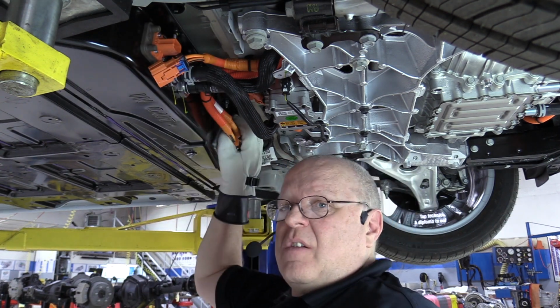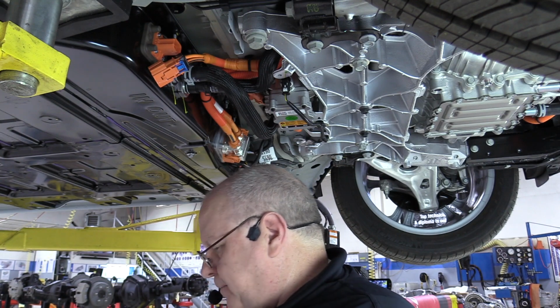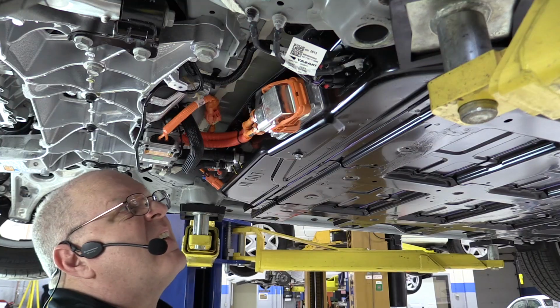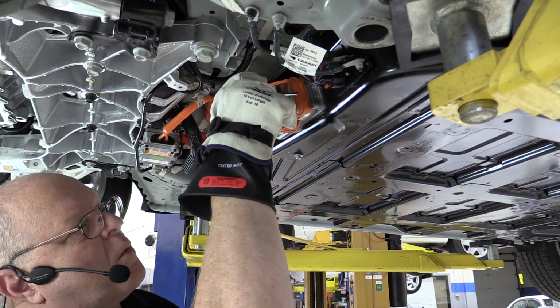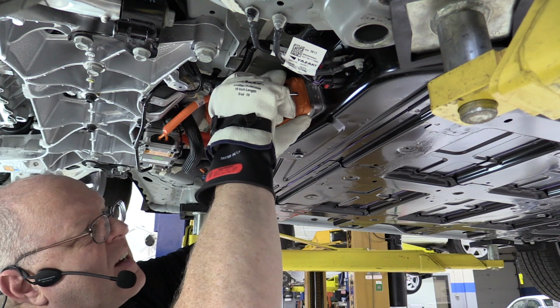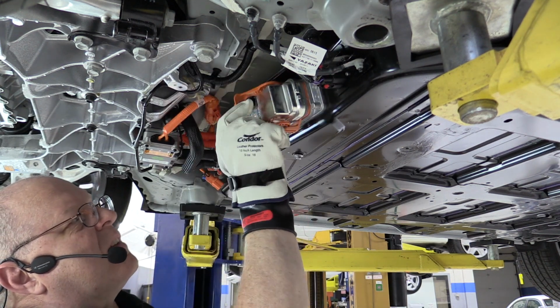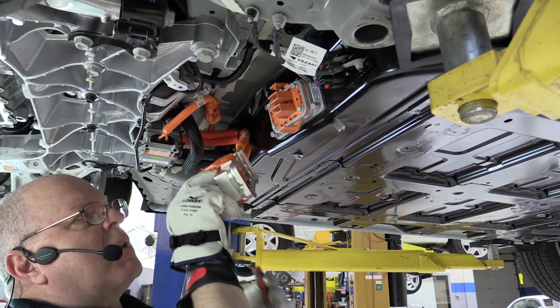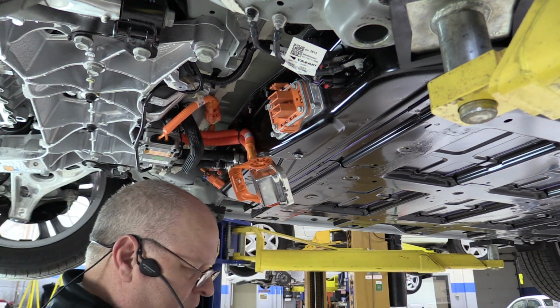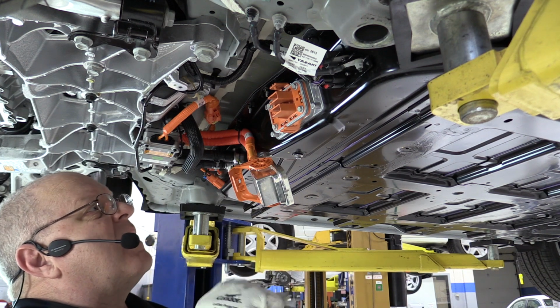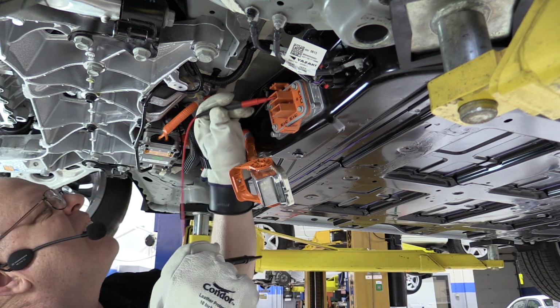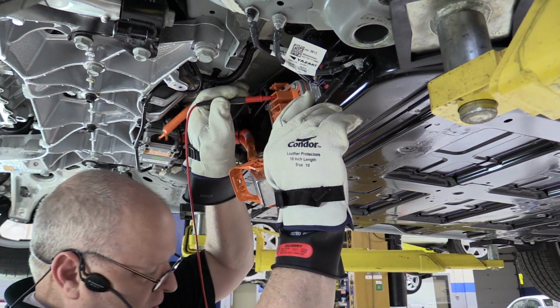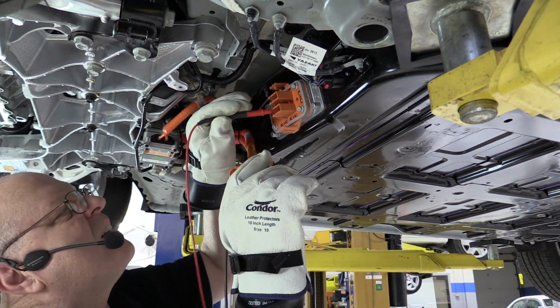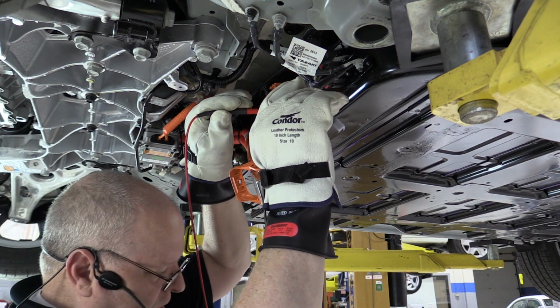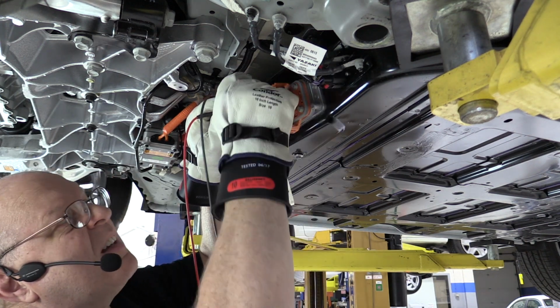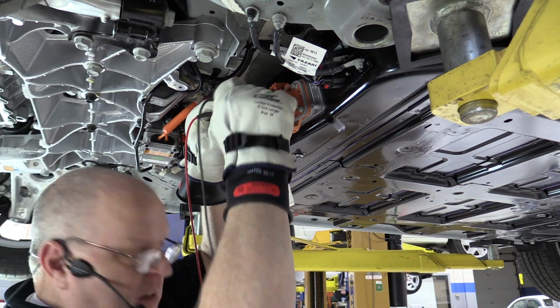And then we'll do the same thing to the big electrical connector over here. So we'll come in and release it just like the one up above. It's the same connector. We'll swing out the lever, pull back. That unplugs the high voltage connector. And then we'll go from terminal to ground, 0 volts, terminal to ground, chassis ground, 0 volts, and terminal to terminal, 0 volts.